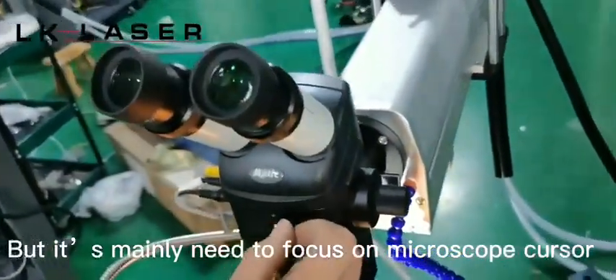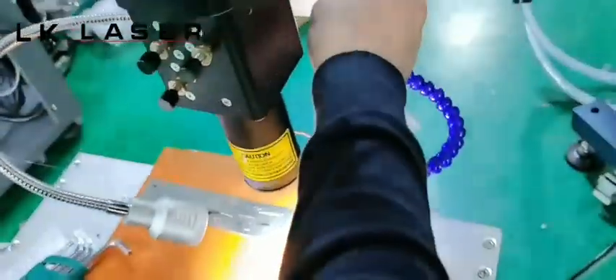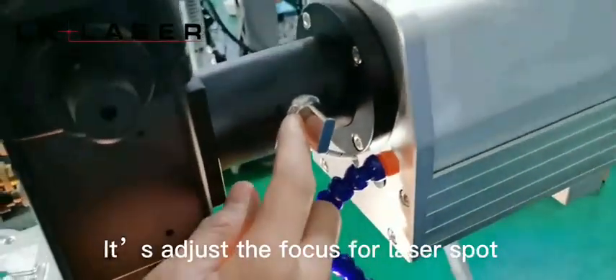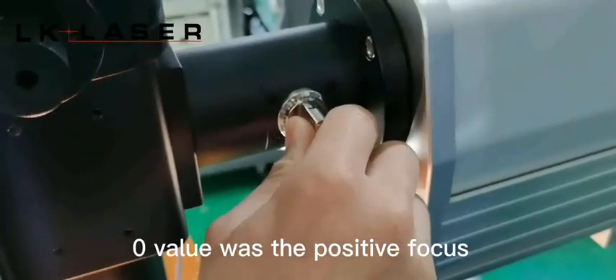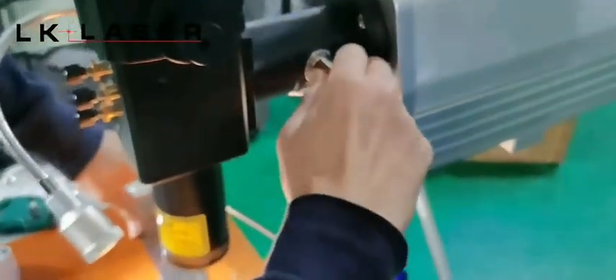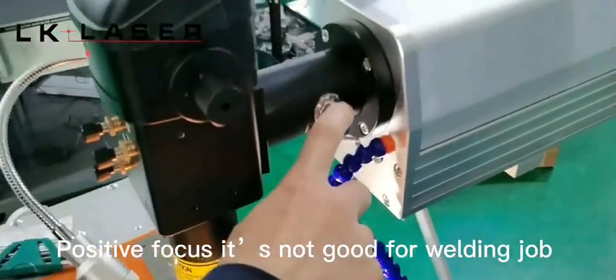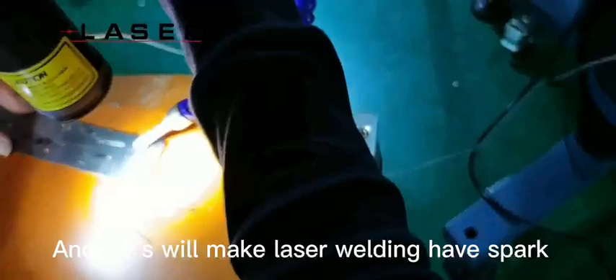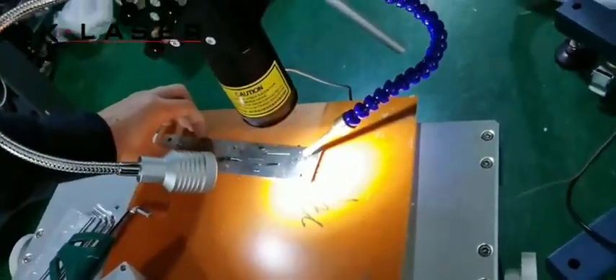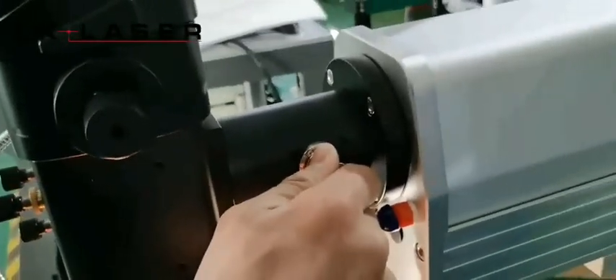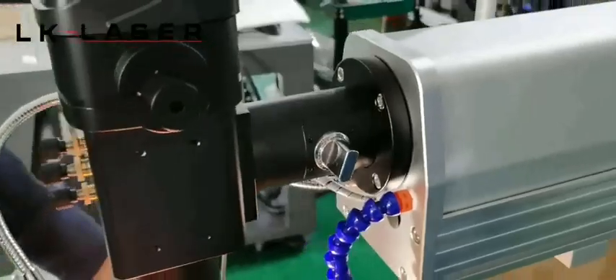But it mainly needs to focus on the microscope cursor. It adjusts the focus for the laser spot. The line value was the positive focus. Positive focus is not good for the welding job. The laser spot is not a circle, so it is not good for welding and melting wire rod, and it will make the laser welding have spark. Make it negative focus to value R. Then the welding position was beautiful and circular.